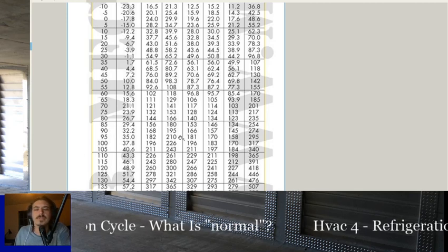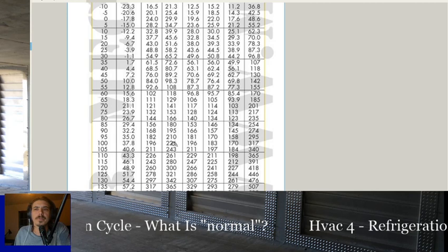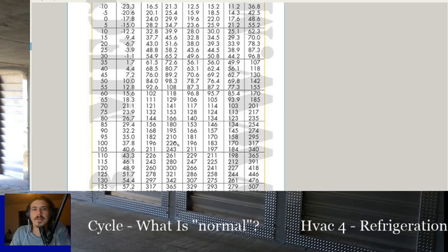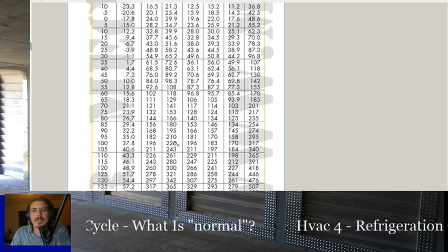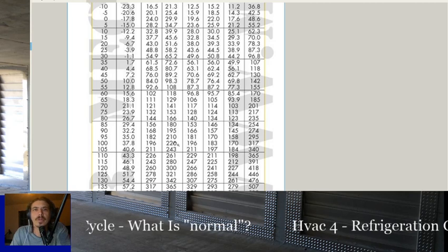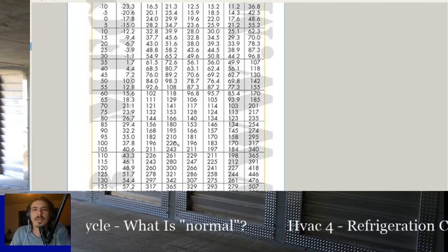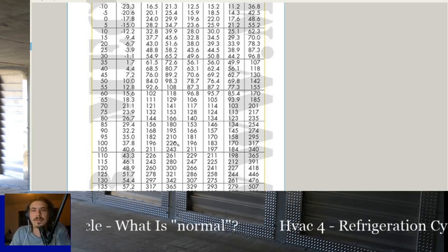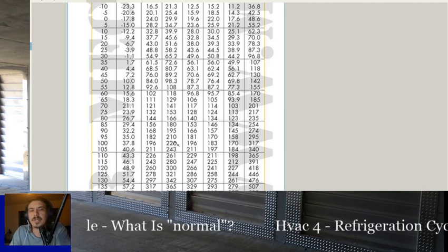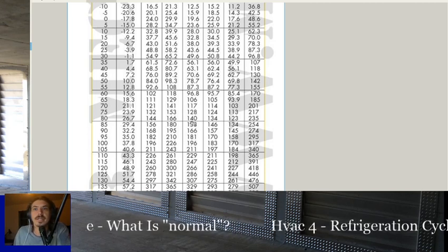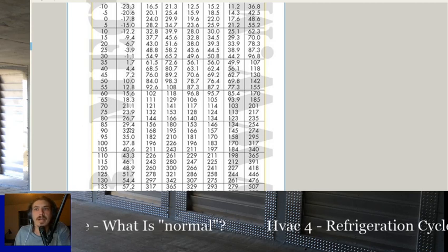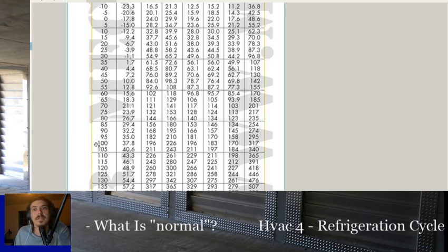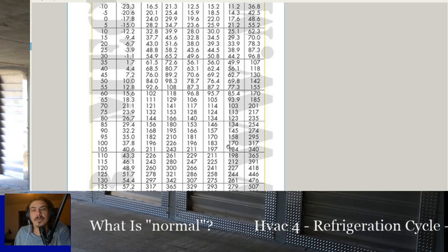But if we add 20 degrees from the outdoor air temperature, we want to try and get 10 degrees of subcooling, right? Unless we're 20, 30 degrees higher than the outdoor air temperature, then we can't give off enough heat to reach that 10 degrees subcooling, because once you get that 10 degrees subcooling, 9 times out of 10, you're going to be 10 degrees hotter than it is outside. So if it's 80 degrees outside, I might expect to read somewhere around 90-degree line temperature. And that's going to be about 10 degrees cooler than my 100-degree saturated refrigerant temperature.